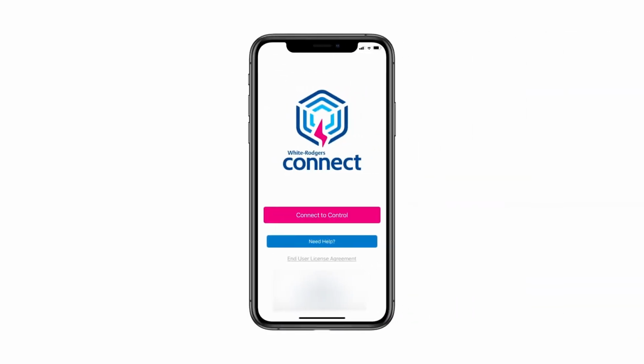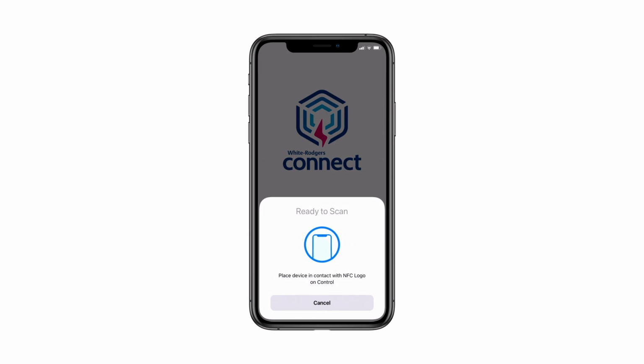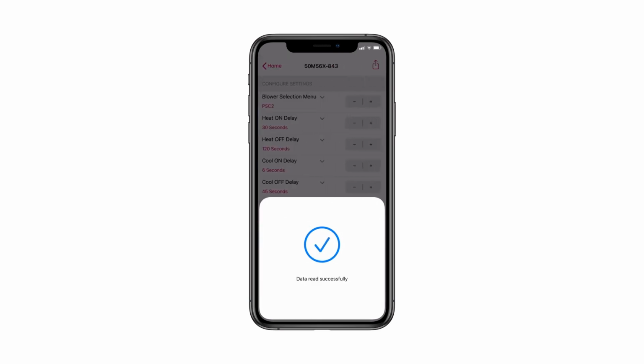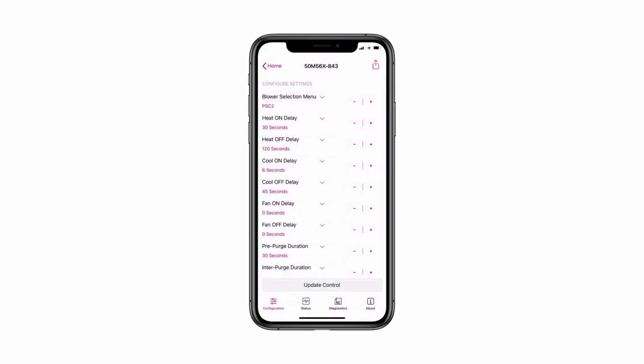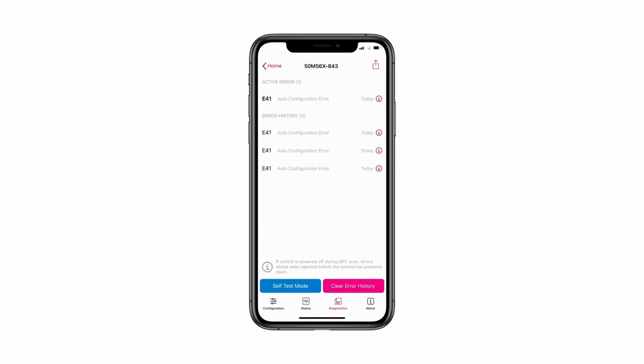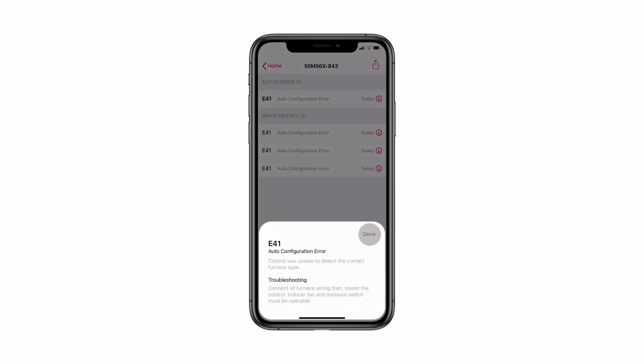Fault code errors can be recalled through the White-Rodgers Connect mobile app. Open the app and select the Connect to Control button. Place the mobile device near the NFC logo on the module and wait until a checkmark appears showing the connection was successful. The app will then display the module's settings configuration page. To see any errors, select the Diagnostics tab. Errors will be listed with the most current at the top. For detailed information and troubleshooting tips, tap the information icon.